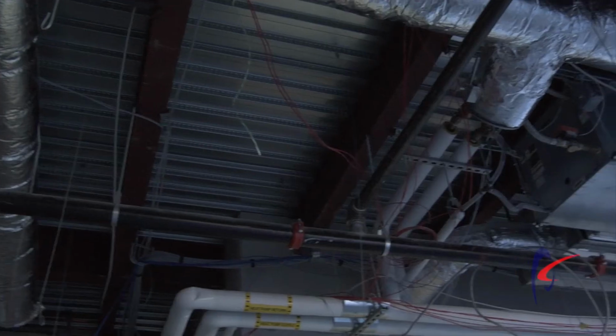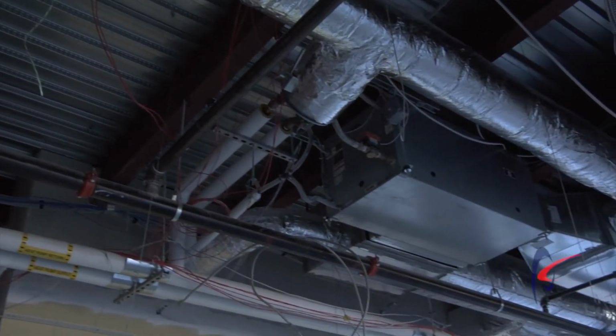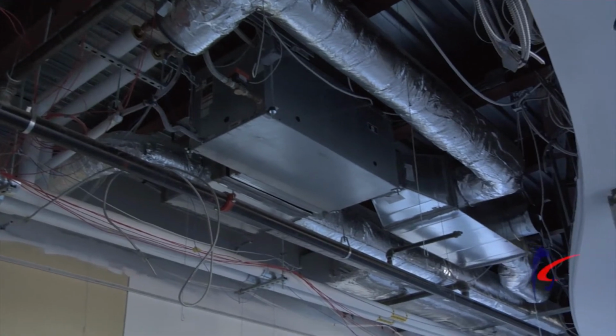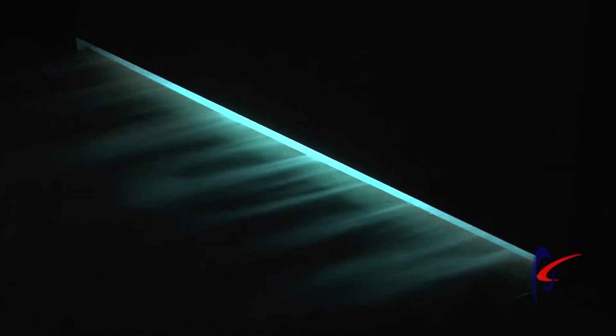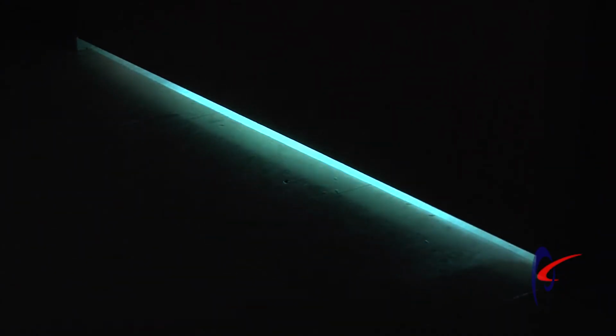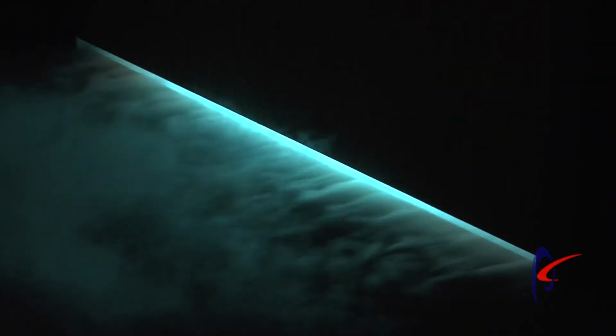Another problem with cross-flow sensors and pressure transducers is accuracy. Typically, when a general contractor is buying a VAV terminal box, they're not paying attention to the accuracy of the pressure transducer. If that's not a very accurate device, then it's not going to be accurately measuring the proper flows for that space, and hence the pressurization of that space could be compromised.